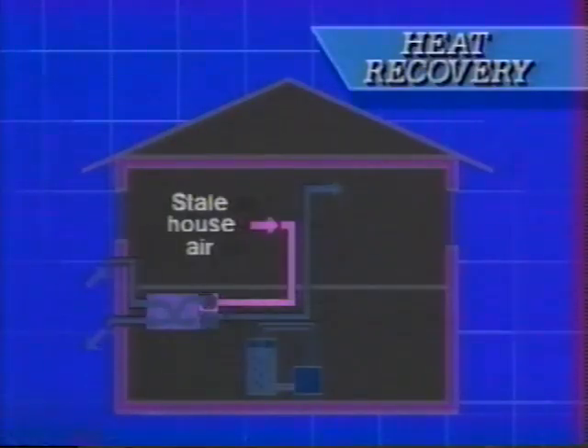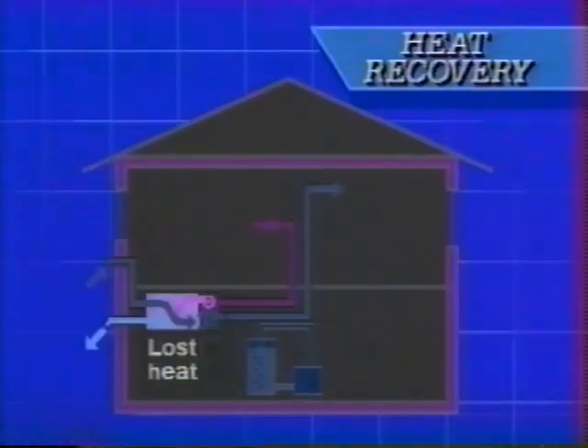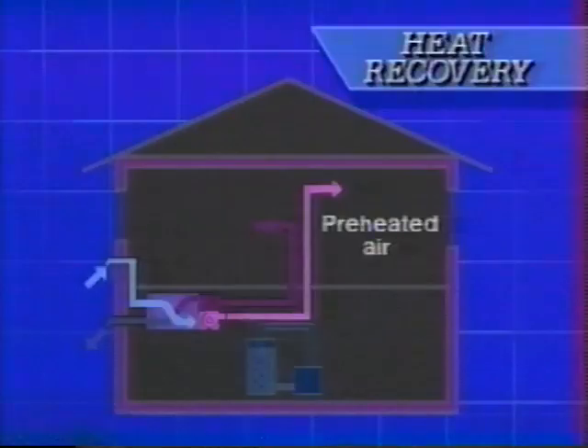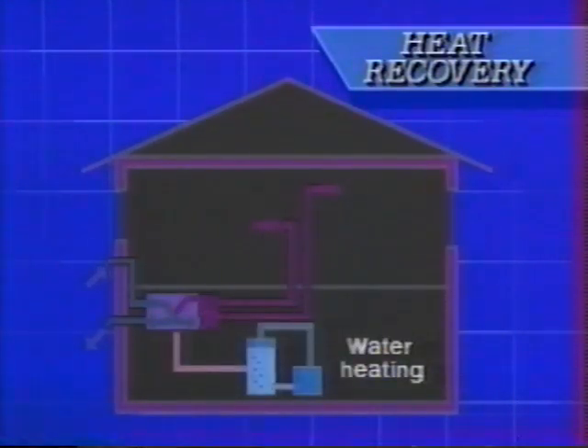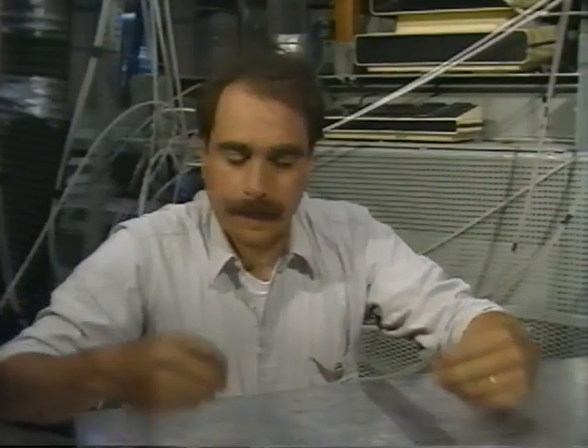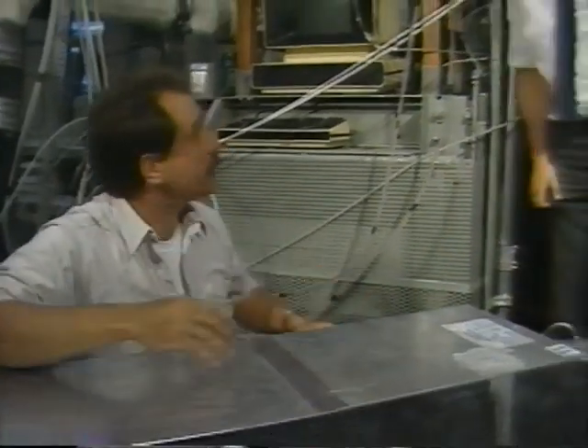The exhaust air stream of the ventilation system will carry as much as 200 CFM, cubic feet per minute, of heated house air. By recovering some or all of the heat being exhausted, significant energy savings will be realized. The heat recovered from the exhaust air stream can be used to preheat the incoming air or to contribute to the hot water requirements of the building. What we're going to be looking at is an option for recovering heat from outgoing exhaust air and using it to preheat ventilation air. And luckily, we've been able to second Colin McGugan from the ORF for a day so that he'll be able to show us around and tell us how this stuff works.